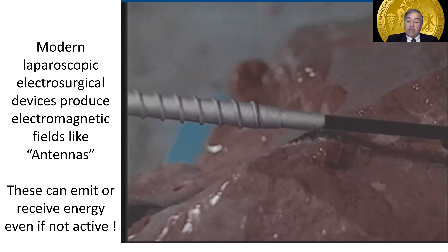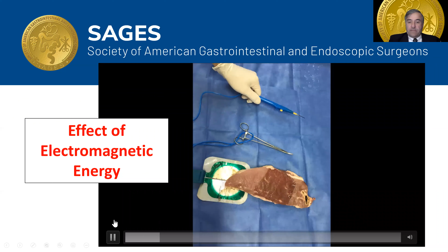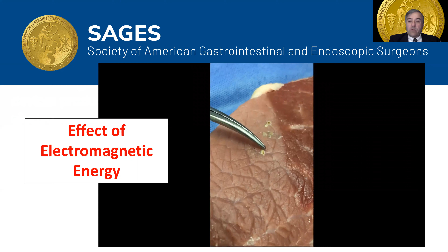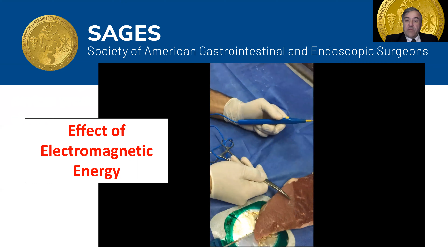The simplest situation in the operating room where electromagnetic field effects come into play is when an electrical cord is wrapped around an instrument. I still do this on occasion. It's such an ingrained practice, but it's dangerous. Both the surgeon and the patient can sustain burns. As you can see here, the instrument becomes electrically charged and can create tissue effects like burns in this case. Although the instrument itself is not connected to any direct electrical contact, it's the electromagnetic field created by the cord that transfers the energy from the activated monopolar instrument.